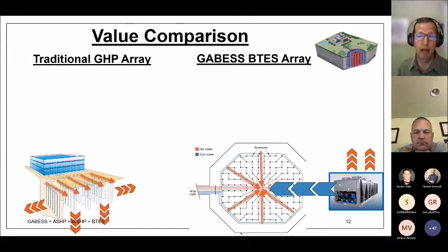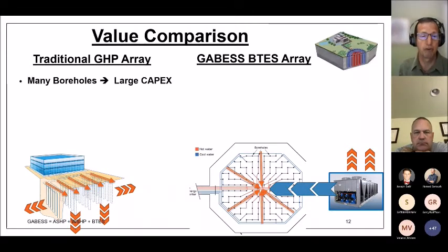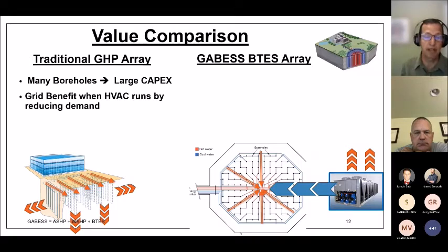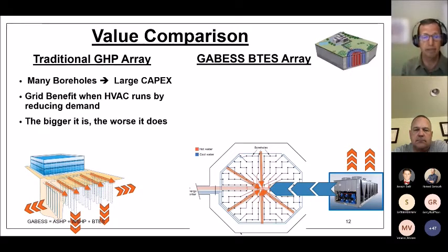Now let's look at the value comparison. We have a lot of boreholes, which means large CapEx, and this is the dominant reason geothermal heat pumps aren't more widely used. There's a grid benefit when the HVAC runs because it reduces demand, but this is very seldom incorporated into the economics. Also, the bigger it is, the worse it does—that's a surface area to volume ratio effect—so it's viewed mainly as a building efficiency tool.